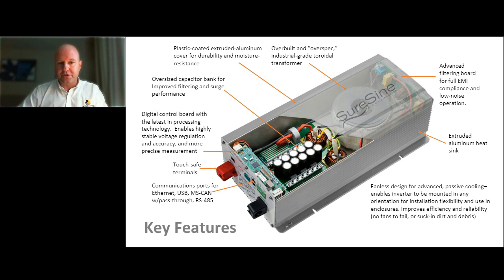And that's really so that you can provide power for continuous loads that may have a little bit of an overrating when they need to start up. And then it's also going to handle products such as motors that have a high inrush current. A locked rotor pulls a lot of current during startup, and we see those industrial applications, valve actuation and industrial process control. They need that surge, and we want to make sure it's going to be delivered here.